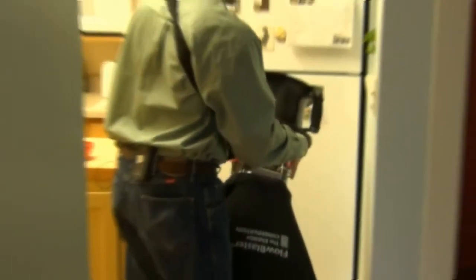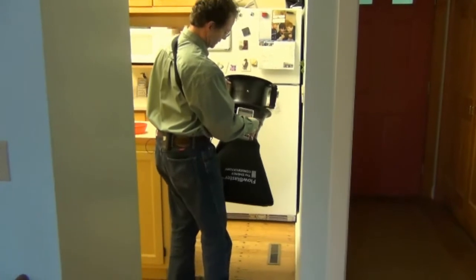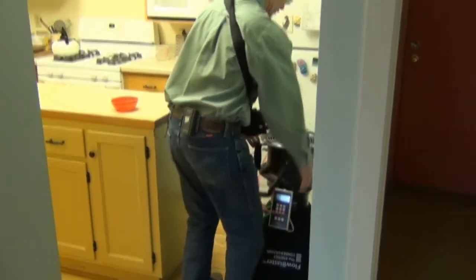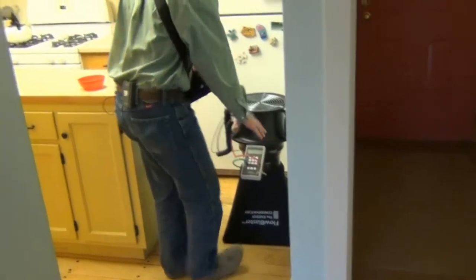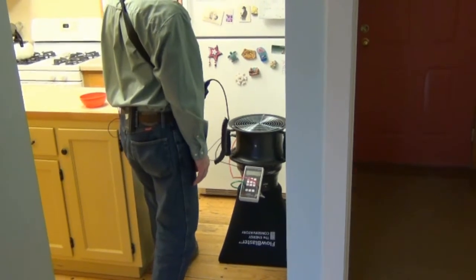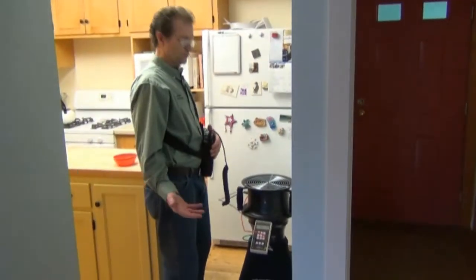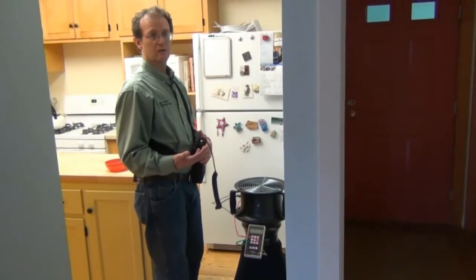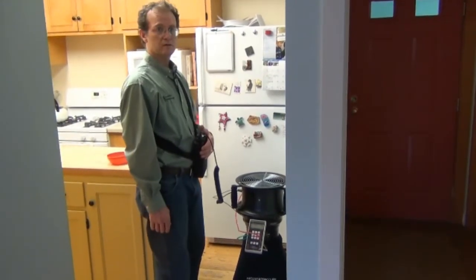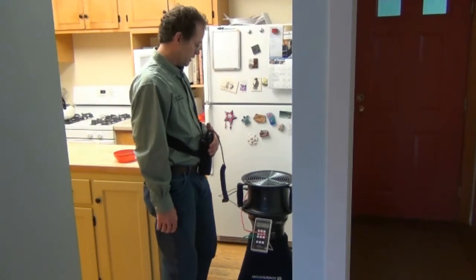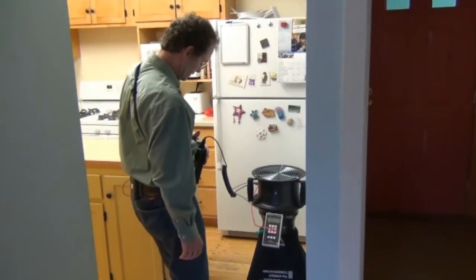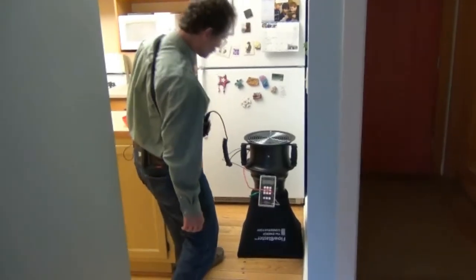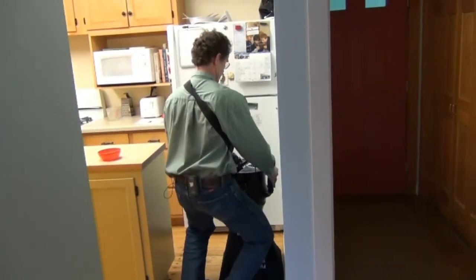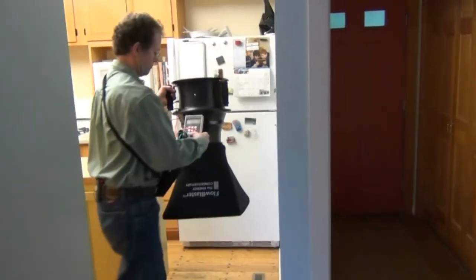Now when I'm ready to measure the flow, I'll hit start fan. Put it over the register. This is adjustable, so we can watch it ramp up here. Because we've got a 2-stage furnace and 30,000 BTUs is the low end, we're getting pretty low flows, and this device is really good for measuring low flows accurately. So we're getting about 21 CFM. So write that down. We can push stop fan and go to the next register.